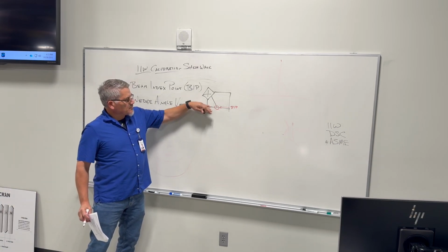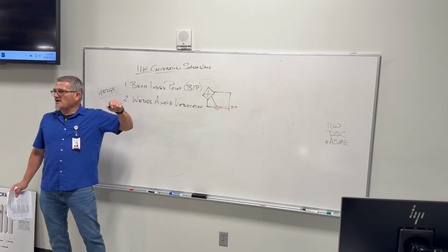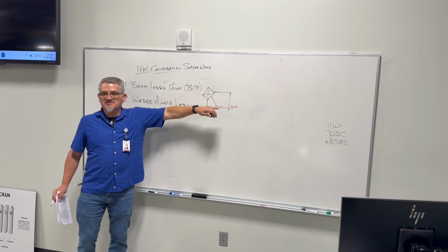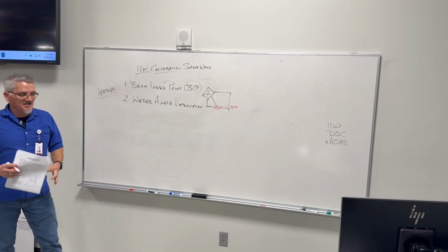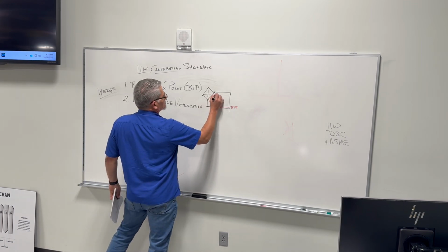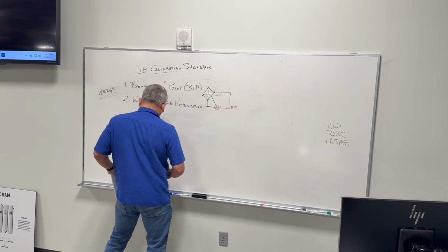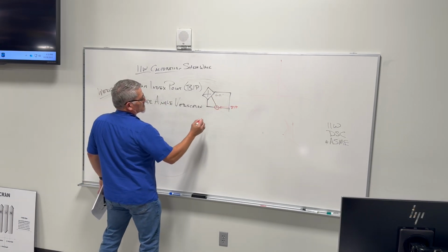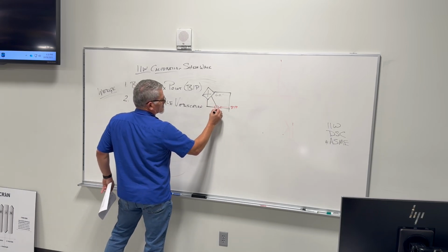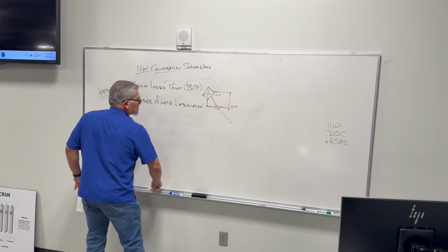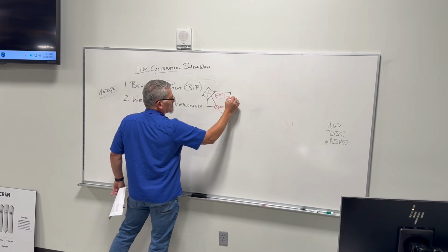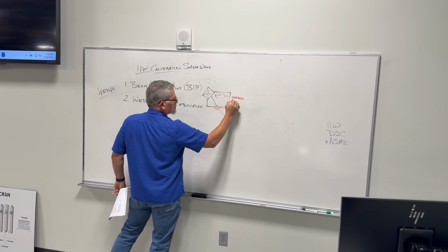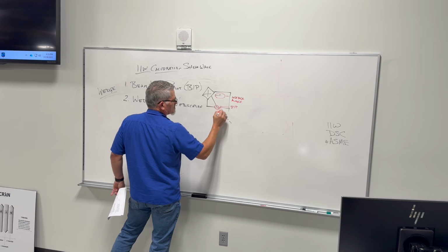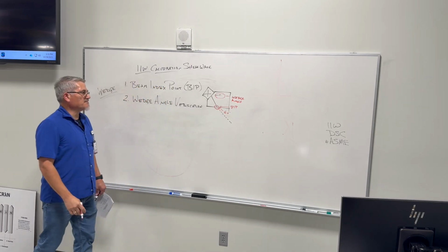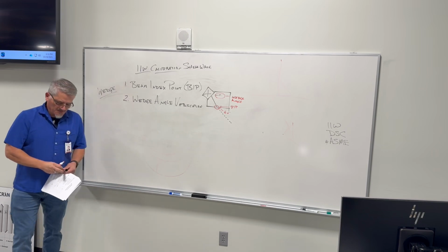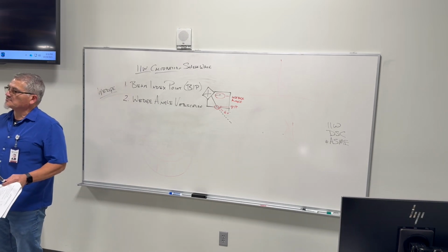What happens over time is this will wear out because this piece of acrylic is consumable. As you scrub it in the pipe, it will shorten, it will change its thickness. As it changes the thickness, it changes the index point, okay? And with that change, you also get a change of angle. In this case, if this is supposed to be a 60-degree wedge, which is the angle of incidence into the material, we're just trying to verify this angle is in fact 60 degrees, okay? So at this point of our steps, you've only verified that the piece of acrylic is good enough to use, okay? It's not worn out, it's fine.